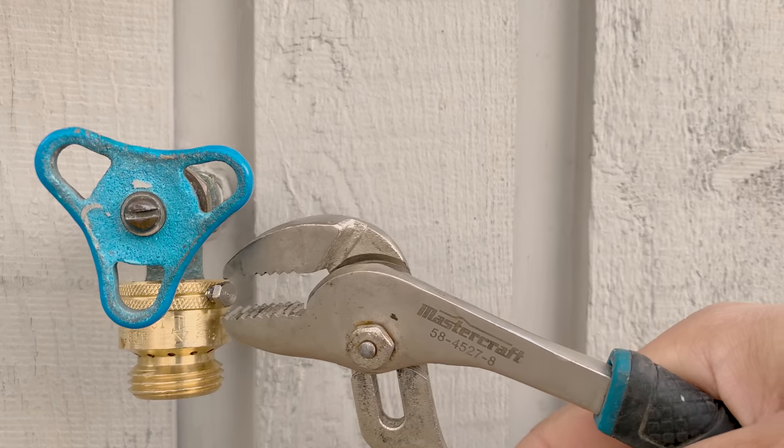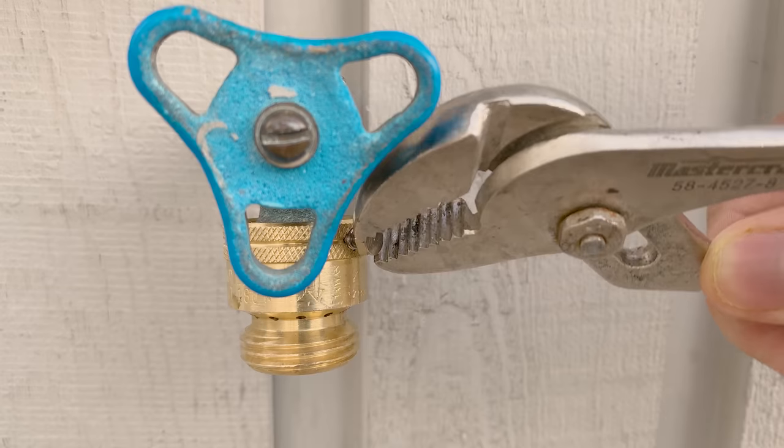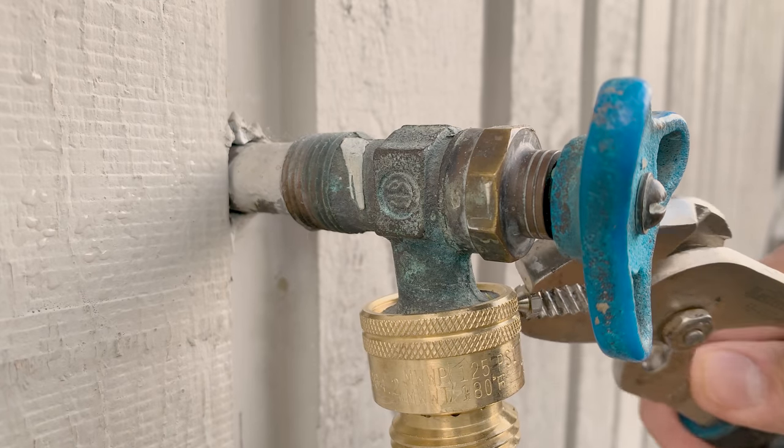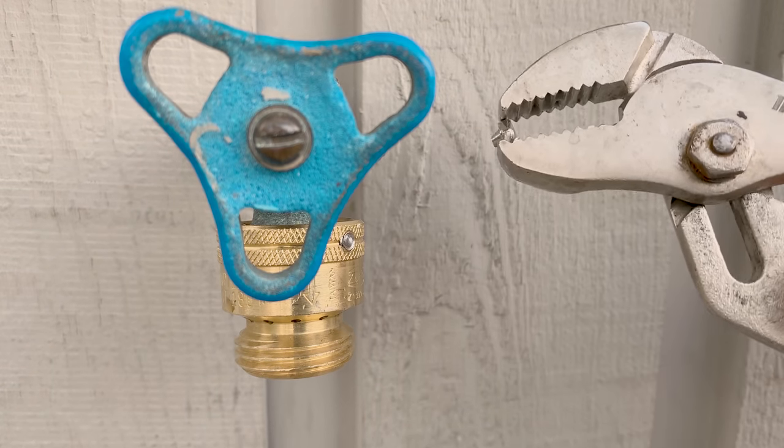A tip here: Do not break the set screw before checking for leaks. It is extremely hard to take the vacuum breaker off once the set screw is broken.